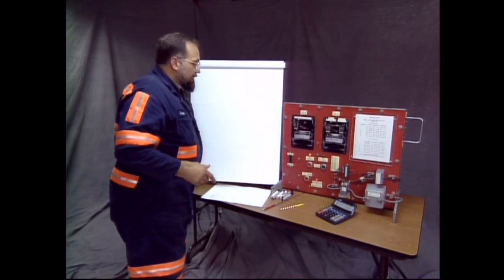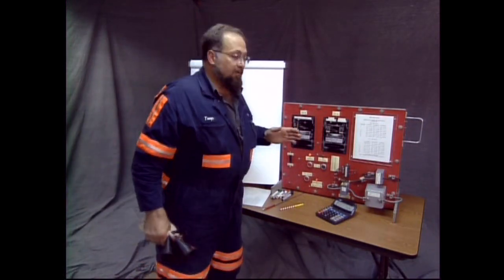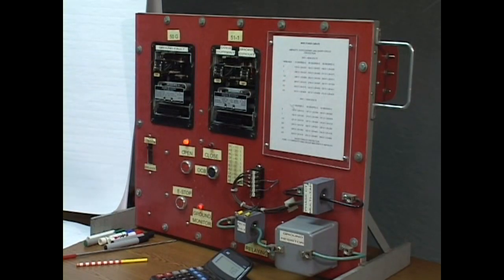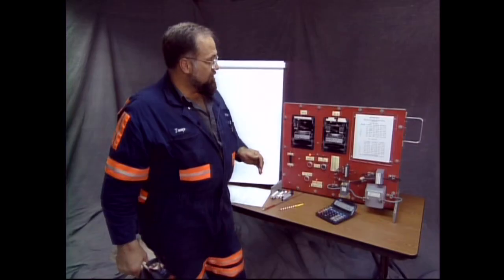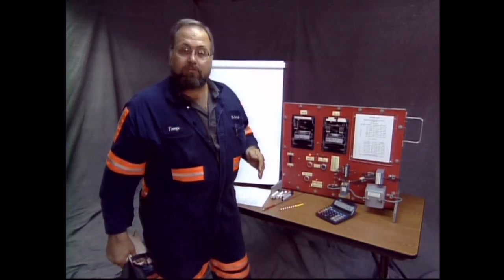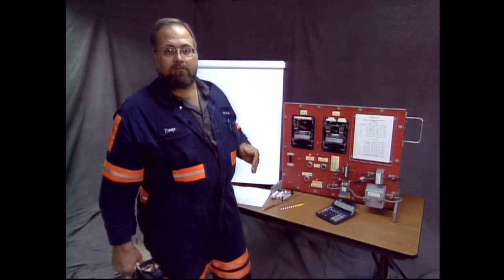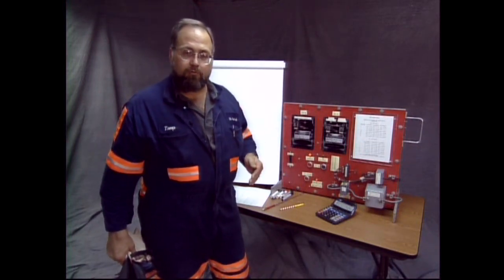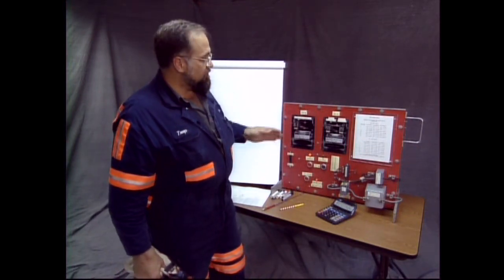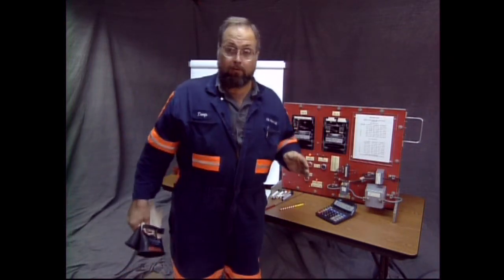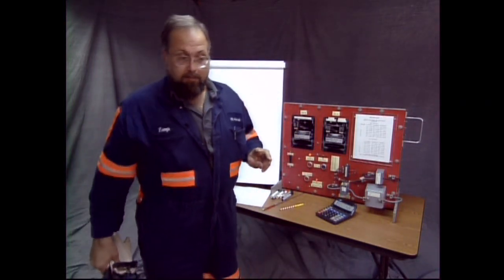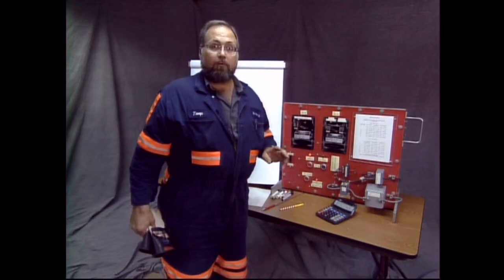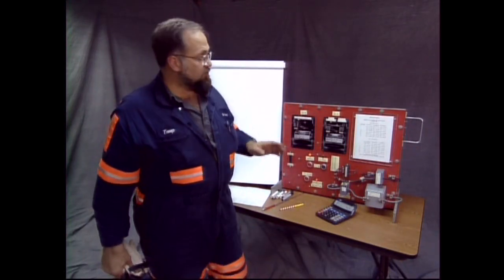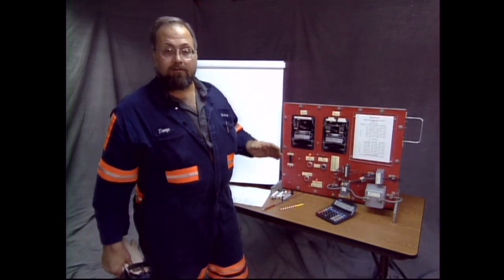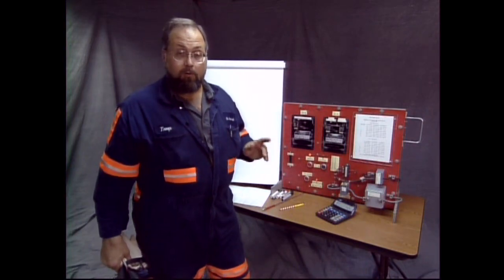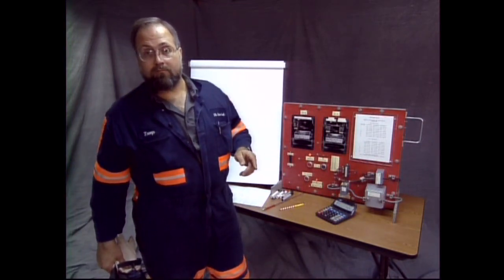You're going to tell the man, I've made a visual examination of my breaker and its auxiliary devices. I'm going to do a manual operation of at least 2 auxiliary devices. And I'm going to check ground continuity to the furthest point controlled by this breaker. That furthest point can only be one of 2 places. The furthest point will be the next switch house, the next vacuum breaker, the next relay that you have on this circuit. Or it'll be the end of the line.